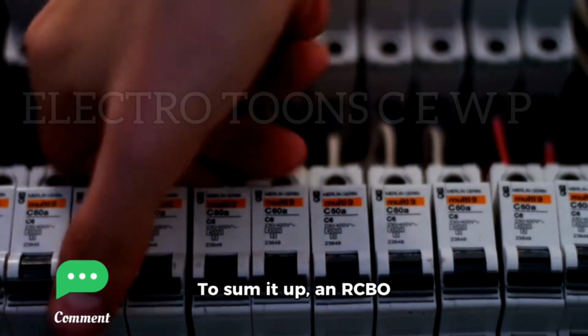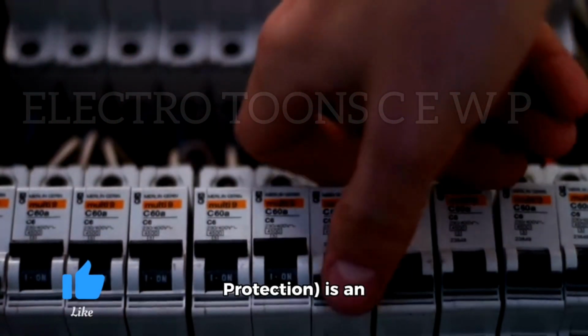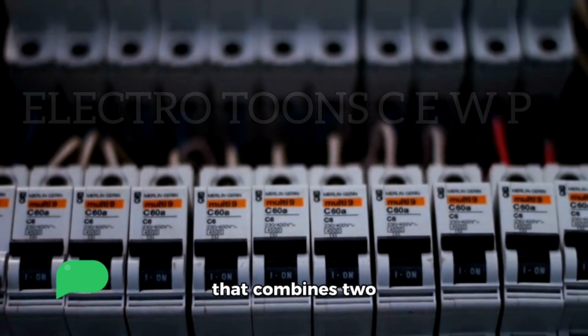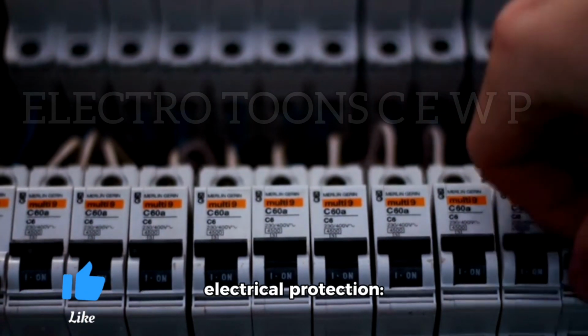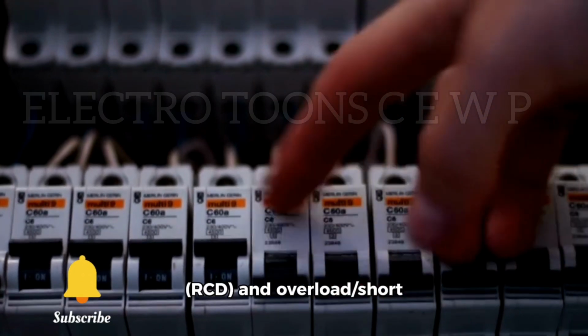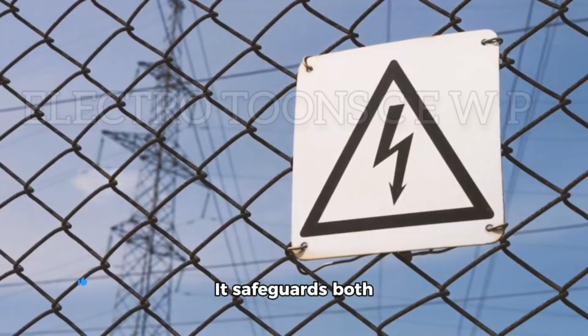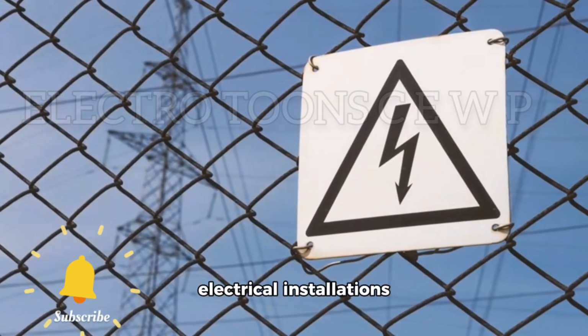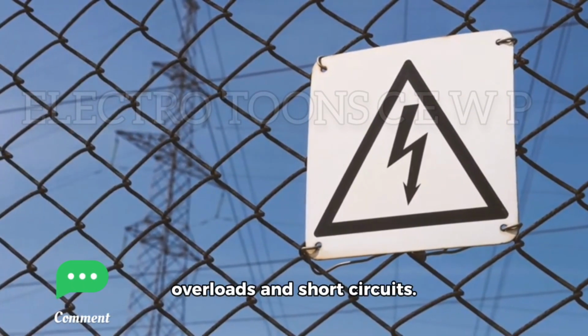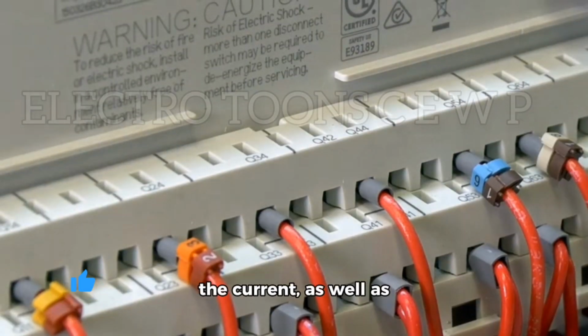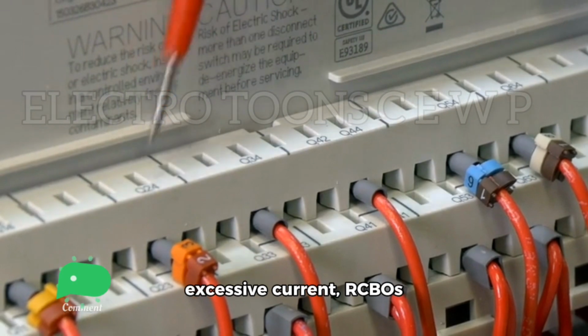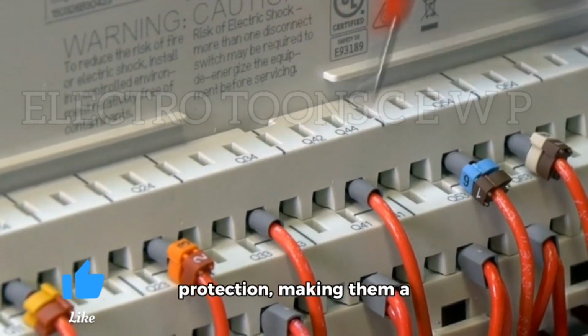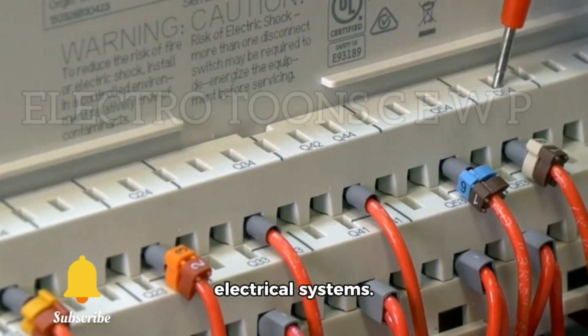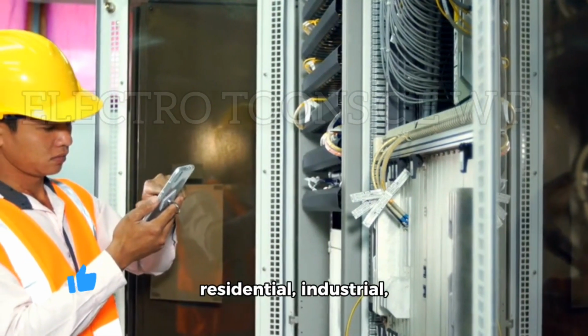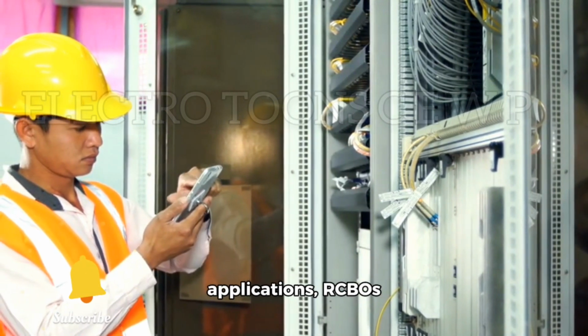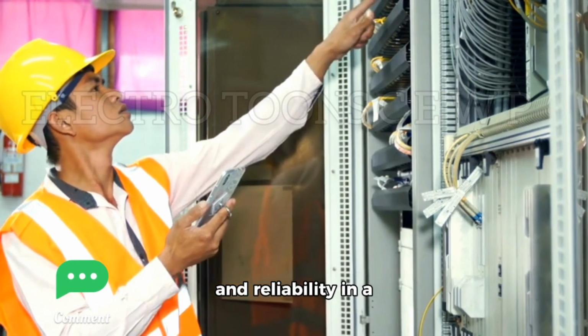To sum it up, an RCBO, residual current breaker with overload protection, is an essential safety device that combines the critical functions in electrical protection: earth leakage protection (RCD) and overload and short circuit protection (MCCB). It safeguards both individuals from electric shocks and electrical installations from the dangers of overloads and short circuits. By detecting imbalances in the current, as well as preventing the flow of excessive current, RCBOs provide comprehensive protection, making them a vital component of modern electrical systems. Whether it's in residential, industrial, or commercial applications, RCBOs ensure electrical safety and reliability in a compact, cost-effective unit.